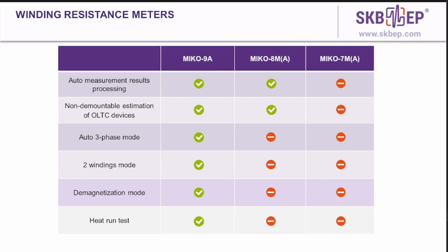Demagnetization mode is a frequently used function. This mode is used before carrying out the open circuit test of a transformer because it's necessary to demagnetize its magnetic core from remnant magnetization. And heat run test. This test checks the transformer coolant system.